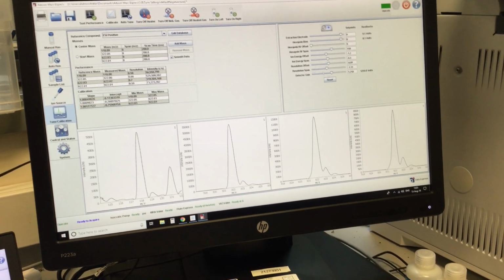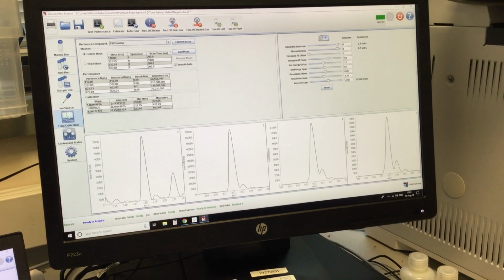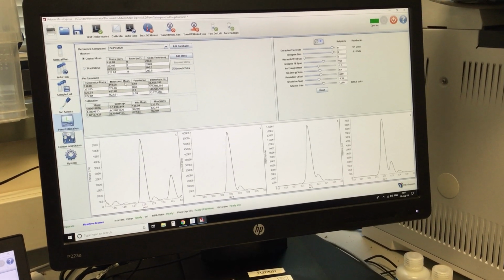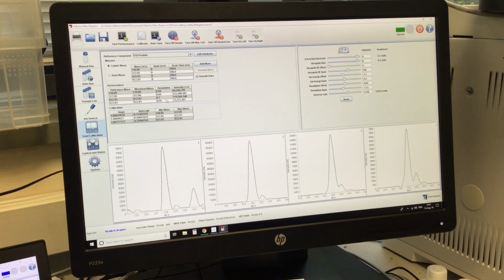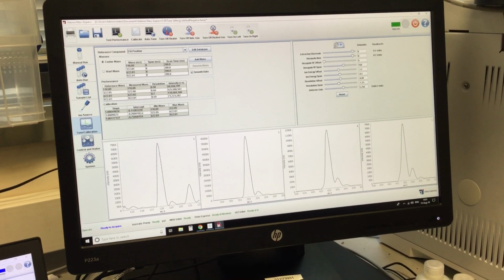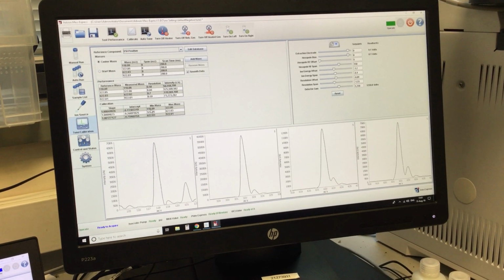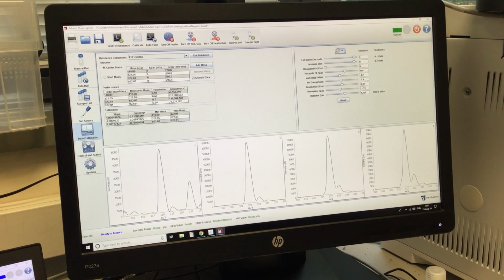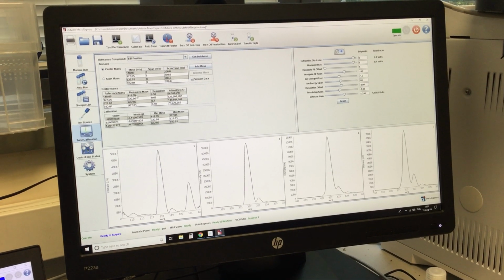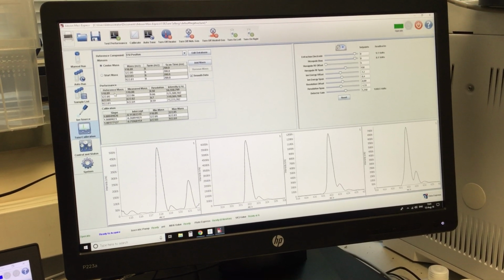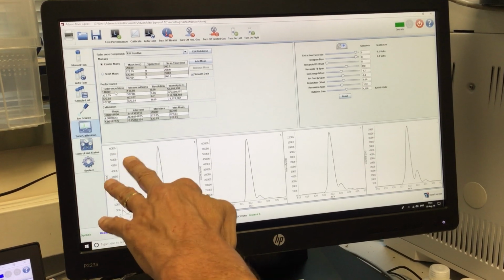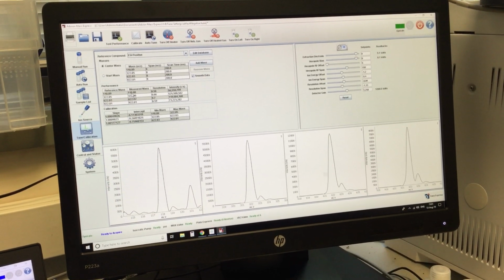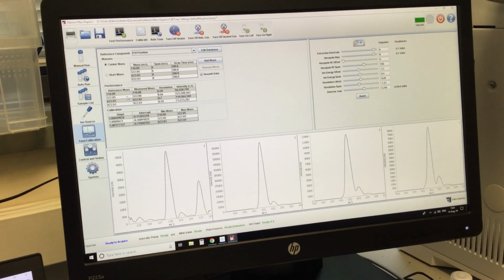Right, so you see once that's gone away, it's filled in this performance table here, and it's also filled in the calibration table. So the performance table is telling us that the measured mass had better be the same as the reference mass, because we just calibrated it. So you would expect these numbers to be the same now.